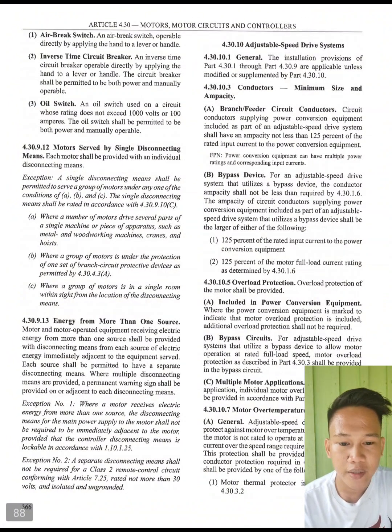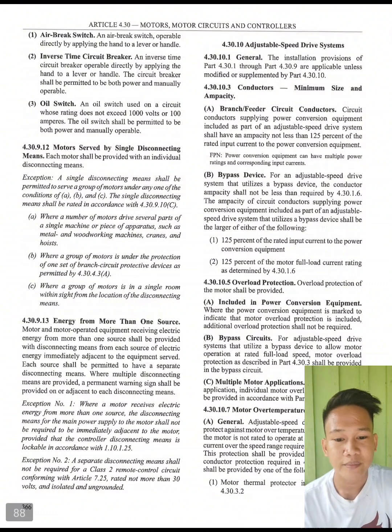First, air-break switch. An air-break switch operable directly by applying the hand to a lever or a handle. Second, we have inverse time circuit breaker. An inverse time circuit breaker operable directly by applying the hand to a lever or handle. The circuit breaker shall be permitted to be both power and manually operable. Oil switch: an oil switch used on a circuit whose rating does not exceed 1000 volts or 100 amperes. The oil switch shall be permitted to be both power and manually operable.